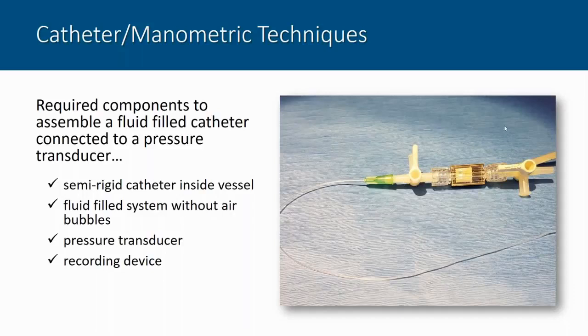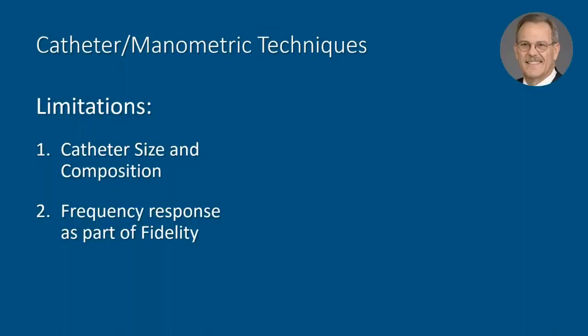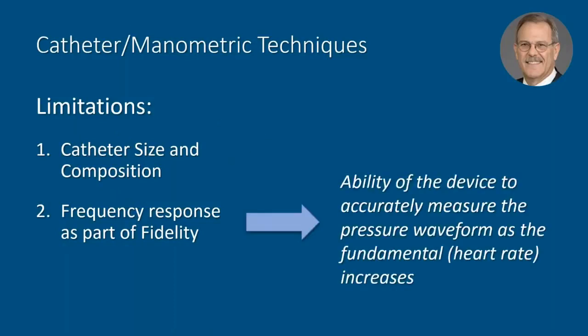The system connects back to a digital data collection recording device. Limitations include catheter size and composition, which affect the ability to cannulate vessels and can affect frequency response. The fidelity of a catheter-manometer system is impacted by the length of the catheter, the diameter of the catheter, and the transducer and recorder system. Generally, the shorter the catheter the better the fidelity, and the larger the diameter the better the fidelity.